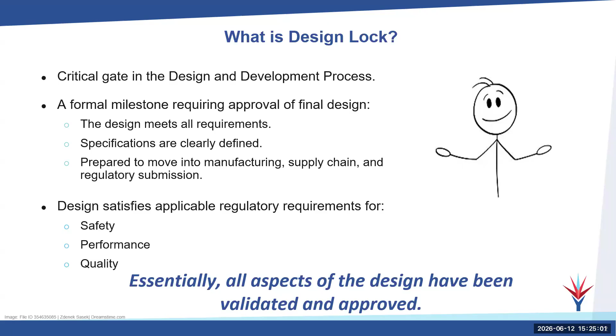This is where you've gone from a really nifty idea and something that you've made in the lab to now a commercializing product. I don't know if that's a word or not, Marissa, but commercializable product, I guess I should say. A formal milestone requiring approval of the final design is one of the biggest documented elements that you need to have in your design control process. You're showing in that formal documentation that the design met all the requirements, specifications are clearly defined, and you're prepared to move into manufacturing, a supply chain, reproducible product, and regulatory submission. So it is a very critical decision-making point. The design has to satisfy safety, performance, and quality. Those are the essential elements to move forward with a validated and approved device.